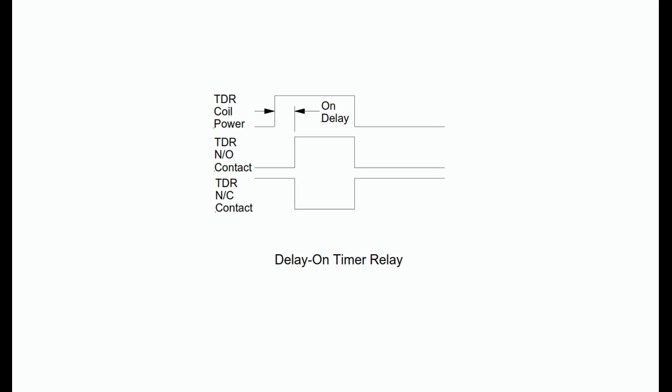This can be either a motor-driven mechanical timer or an electronic timer. When the time value contained in the timer reaches the preset value, the relay energizes. When this happens, all normally open (NO) contacts on the relay close and all normally closed (NC) contacts on the relay open. Notice also that when power is removed from the relay coil, the contacts immediately return to their de-energized state, the timer is reset, and the relay is ready to begin timing again the next time power is applied.